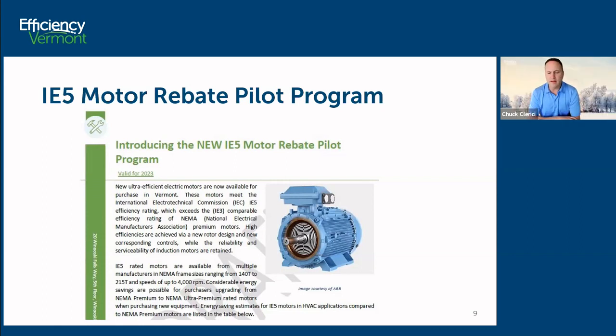In Europe, they typically have energy efficiency standards that are a bit ahead of ours, and that is the case with motors. So the motor manufacturers have been making motors going into Europe that exceed our NEMA premium efficient standard, and they use a different motor efficiency rating system, using IE3, IE4, IE5. So we're essentially moving from IE3 to IE5 now, which is a two-step jump, which is very exciting for us because we have a window of opportunity between now and whenever the US federal government decides that IE5 will become the new standard.